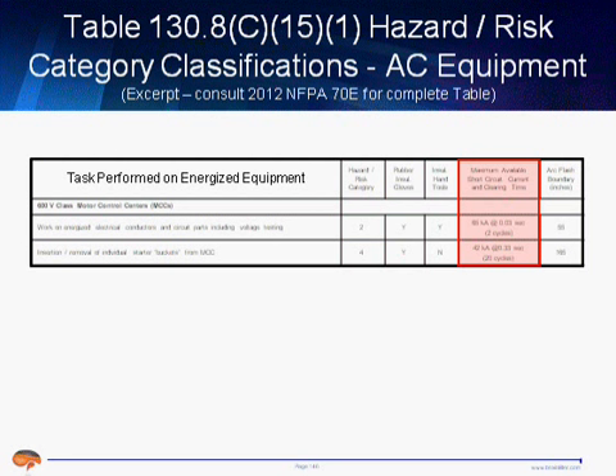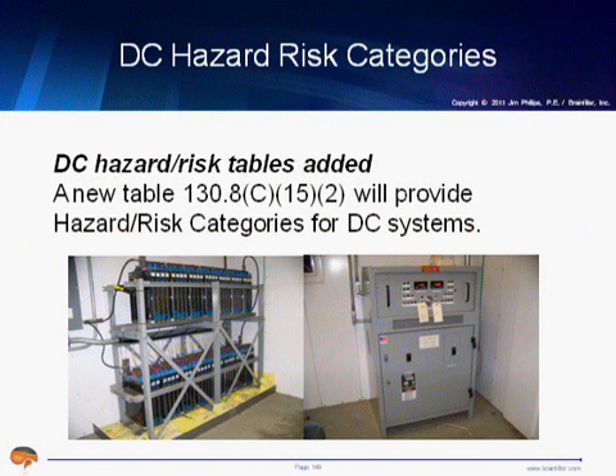So we're going to have the upper limits of short circuit current and the upper limits of clearing time included in this column, and then we're also going to have the arc flash boundaries included. So you're going to see some of the good information being directly part of the table, and that eliminates some of the confusion of referring to the footnotes, as well as, well, some people didn't know to refer to the footnotes. And so then you could look up your equipment and your task, and all the information is there for you.